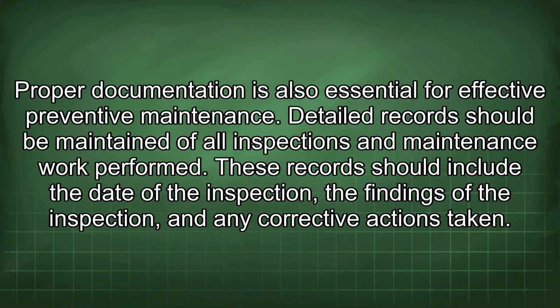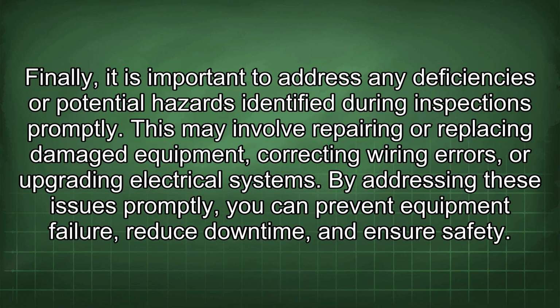Proper documentation is also essential for effective preventive maintenance. Detailed records should be maintained of all inspections and maintenance work performed. These records should include the date of the inspection, the findings of the inspection, and any corrective actions taken. Finally, it is important to address any deficiencies or potential hazards identified during inspections promptly. This may involve repairing or replacing damaged equipment, correcting wiring errors, or upgrading electrical systems. By addressing these issues promptly, you can prevent equipment failure, reduce downtime, and ensure safety.